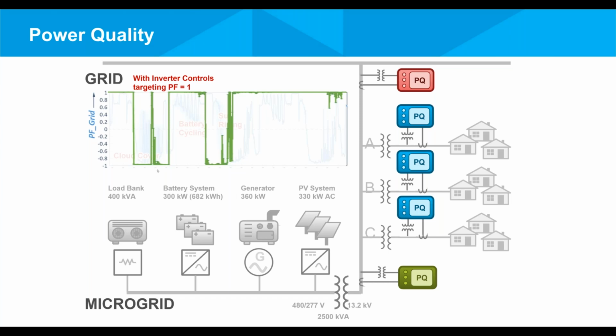And some of the things that the microgrid is doing here is, in the case of appliances consuming reactive power in the homes, there's a need for reactive power to counterbalance the inductive load. There's a need for capacitive VARs, reactive power, to counter the inductive loads in the homes. So it's either the reactive power is being provided by the grid or by the energy storage. So once the inverters are set and the microgrid is set to control the power factor, there's a chance that the microgrid is providing VARs, reactive power, to ensure that the power factor is as close to unity as possible.